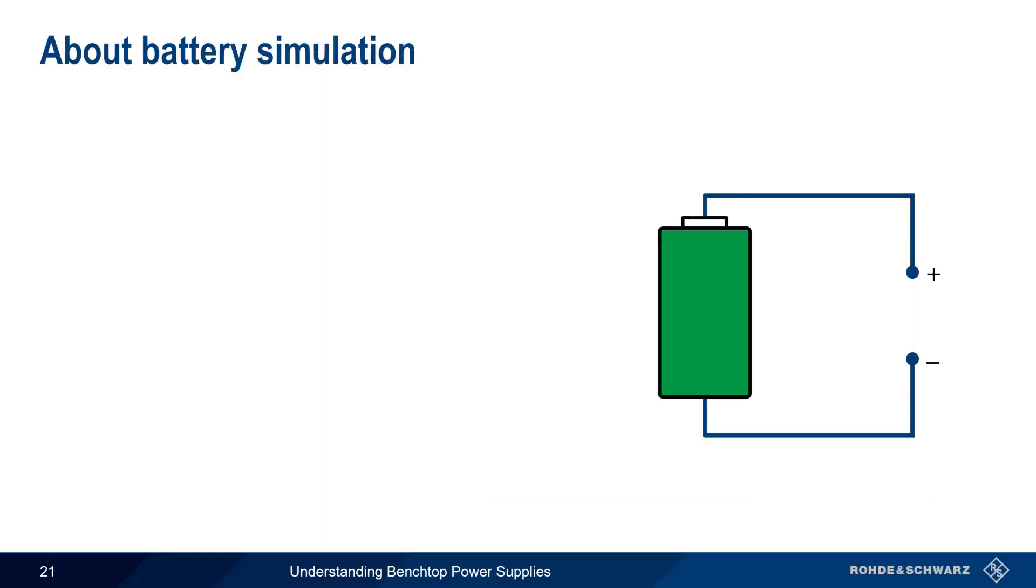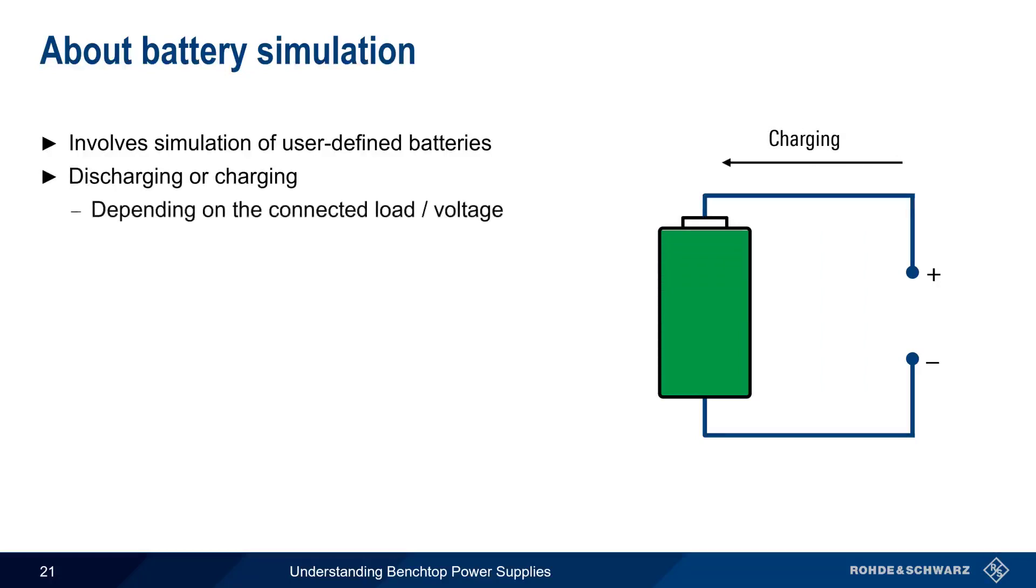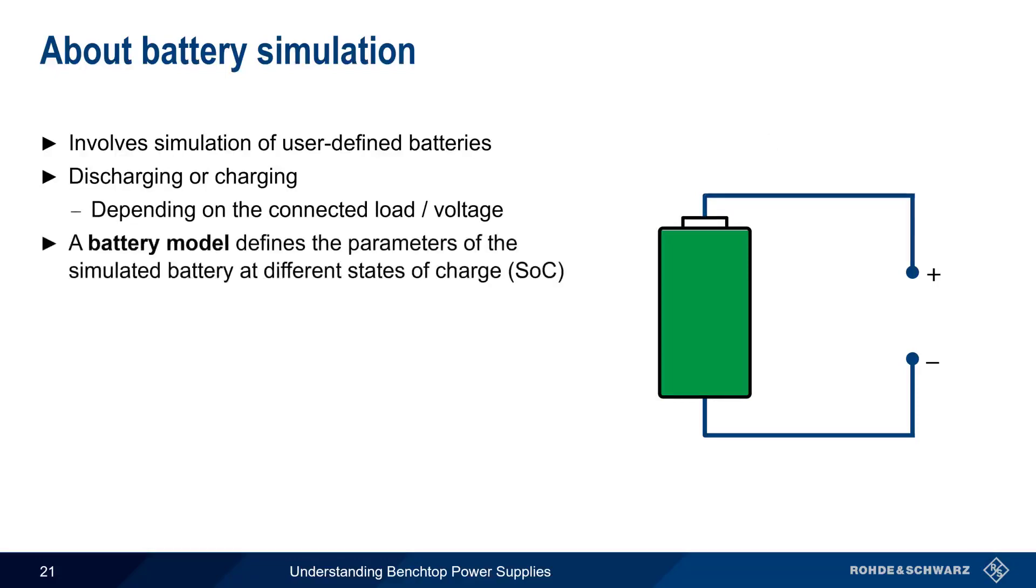Although sync mode can be used to test batteries, some power supplies support simulating a battery with user-defined parameters. The simulated battery then discharges or charges depending on the load or voltage present at the power supply terminals. In order to do this realistically, a battery model is required. This model defines the parameters of the battery at different states of charge. This is important because all batteries behave differently at different states of charge.